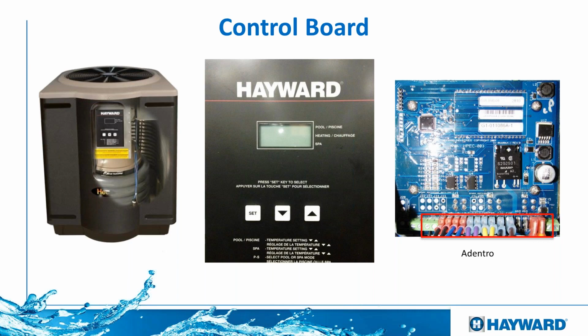Then we have these two purple ones, which are flow. Okay, so flow will be related to the pump. Maybe it doesn't have a full prime, maybe it's off, maybe it's not working, or simply we have a dirty filter or a valve on the wrong position, or maybe a complete open bypass. So that's the kind of things that we're going to have to look at.